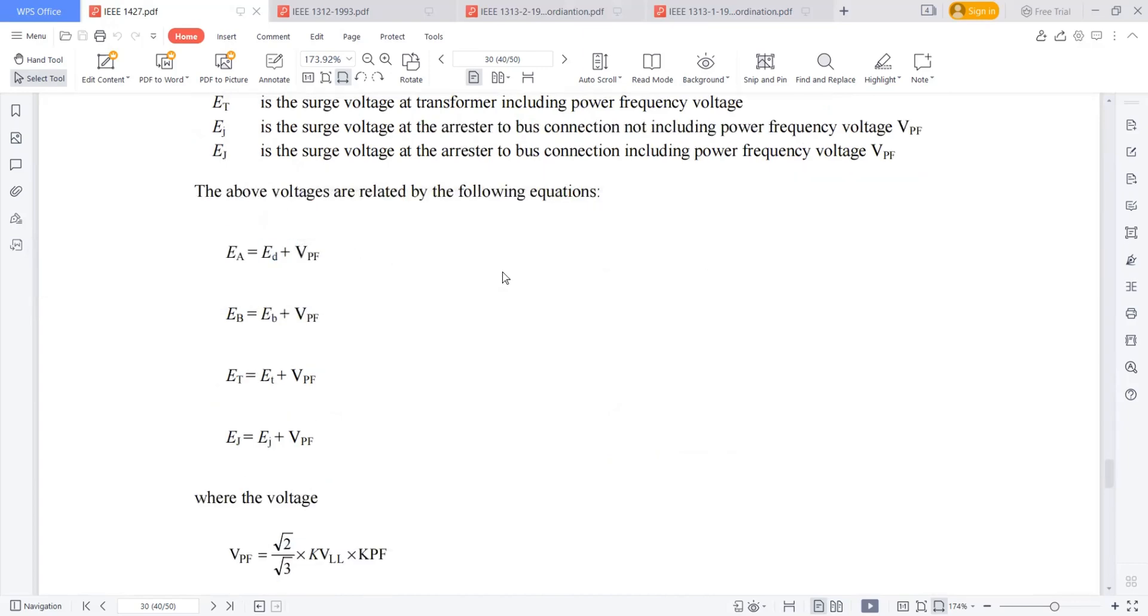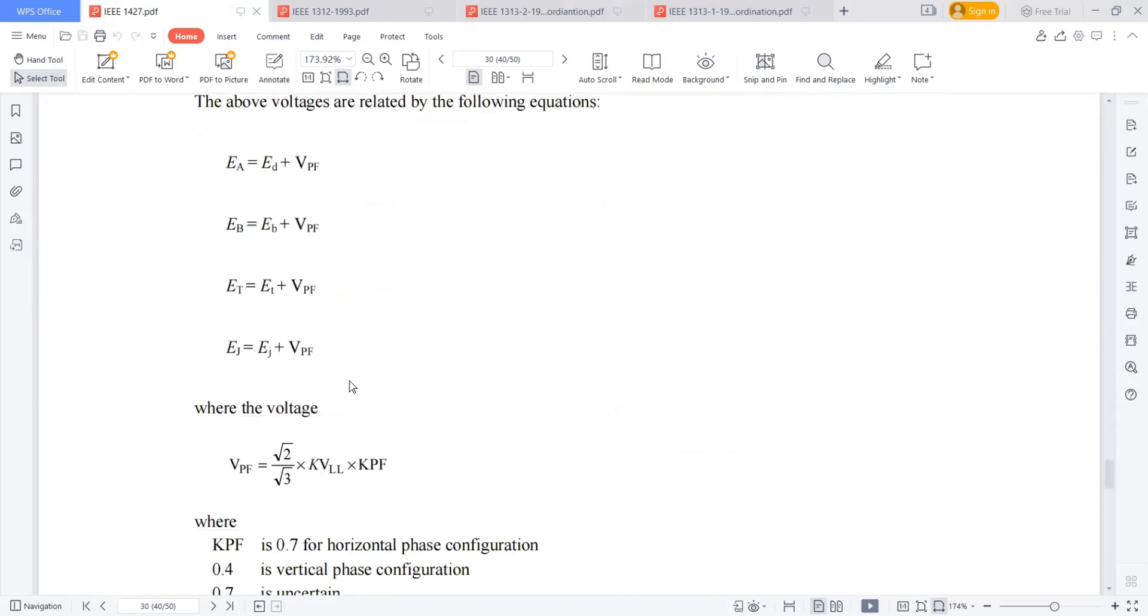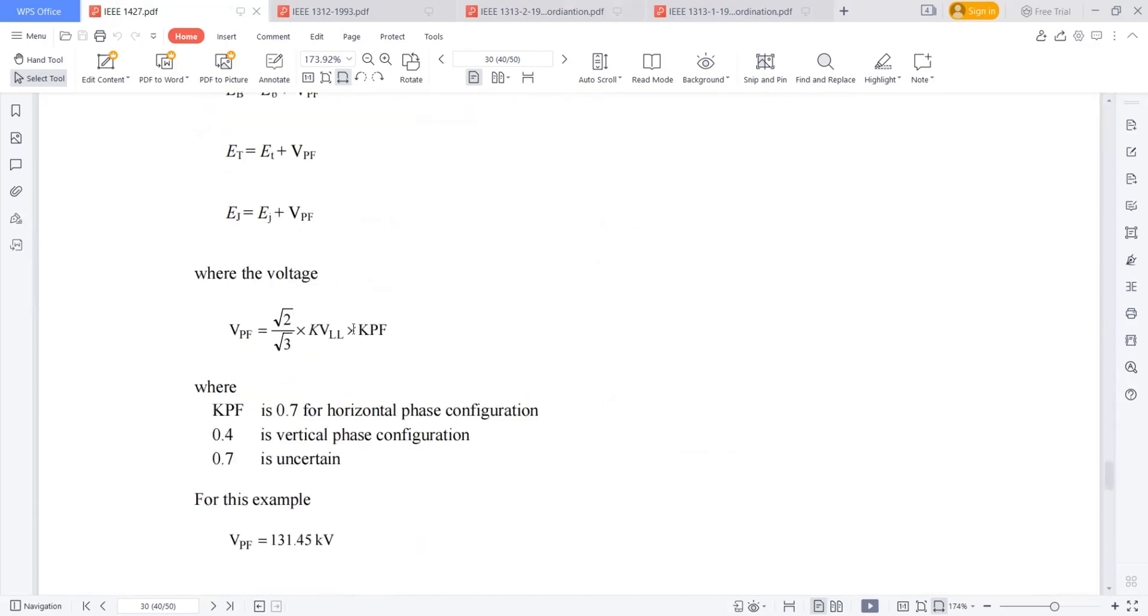VPF, generally you will get from the power frequency withstand voltage. What is the power frequency withstand voltage? Line to line voltage into root 2 by root 3. And again, it depends upon the type of the configuration. If horizontal configuration, mentioned 0.7, if it is vertical 0.4. So the VPF, the power frequency withstand voltage of 220 kV to 230 kV line is 131.45 kV.